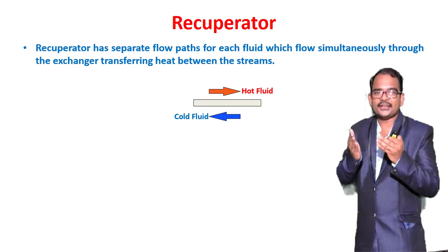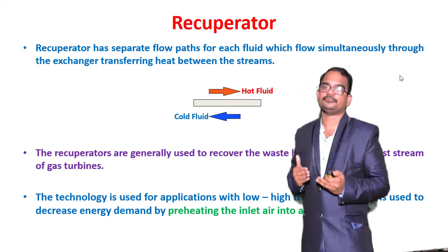So recuperators are generally used to recover the waste heat from the exhaust stream of gas turbines. The gas turbine exhaust will be utilized by means of a recuperator. This technology is used for applications with low to high temperature heat recovery, and is used to decrease the energy demand by preheating the inlet into the system. So the purpose of this recuperator is to preheat the air entering into the combustion chamber, thereby improving the efficiency of the process.